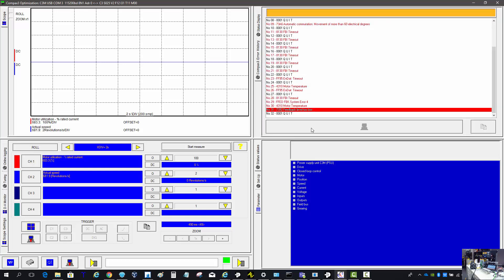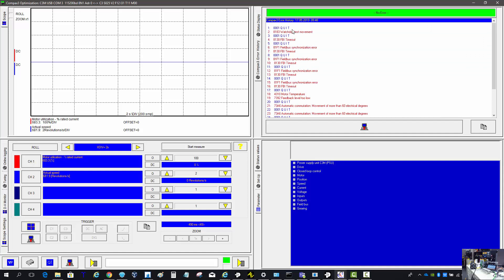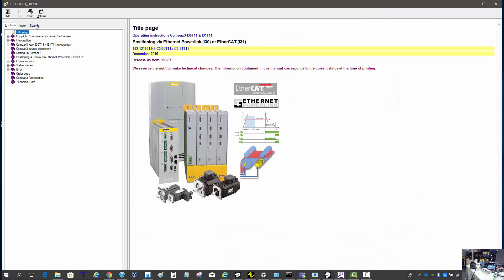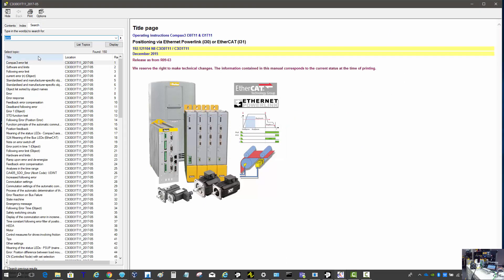The Compax 3 error history will upload the last 31 different errors. They're separated by a quit, which is the error acknowledgement, so you can have multiple errors at the same time. Here, motor temperature and feedback too low — the cable was unplugged. The motor temperature is a normally closed thermal switch inside the motor that opens up when it gets too hot. To look up an error, you can go into the help file and search 'error' to open up the error list.